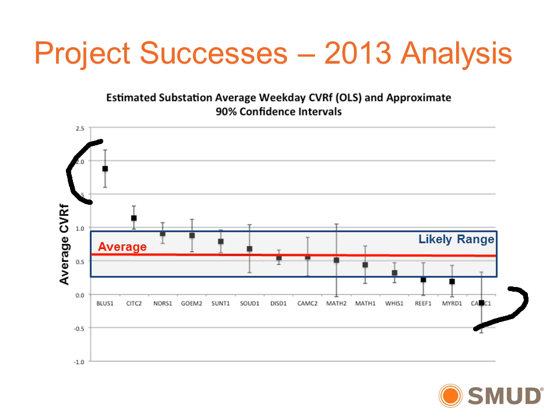But as Tom pointed out, a lot of our loads are now moving to more electronic modes like LEDs, and even the fluorescents are different. It's not a linear relationship, so it's hard to say exactly how those turn out. But across our 14 subs, you can see by this box the average conservation voltage reduction factor was 0.6. In other words, for a 2% reduction in voltage, we should see a 1.2% energy savings.